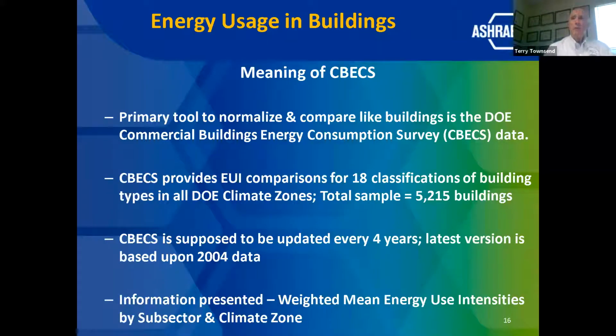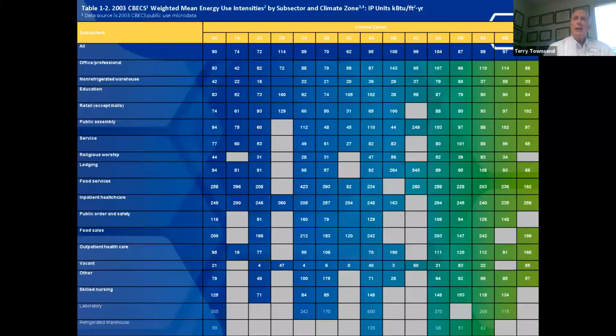Now, how many of you are familiar with CBECS, the Commercial Building Energy Consumption Survey? It was stopped for a few years because of budget constraints, but it has been started back up. On average, we look at over 5,200 buildings. They look at 18 different classifications in the climatic zones. What they look at is the energy utilization index for various building types. This gives you a summary for the different climatic zones and building types of what the EUI number is, based upon kBtu per square foot per year.